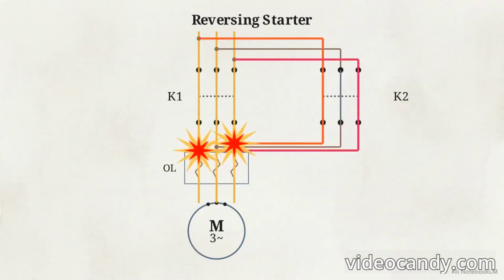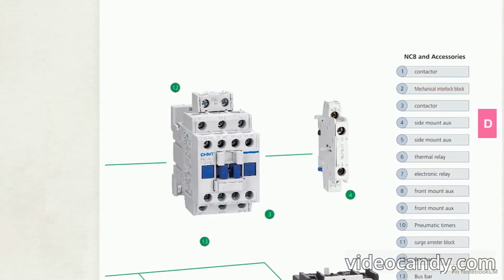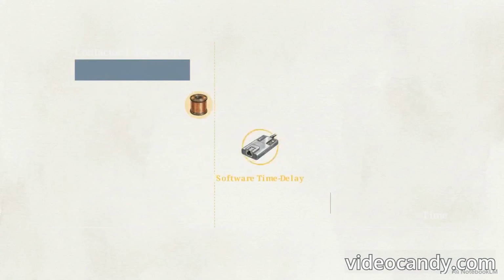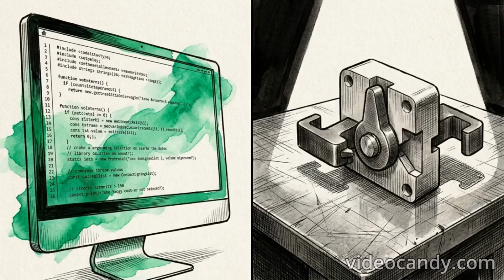A more complex application is the reversing starter. To reverse the rotation of a three-phase motor, you need two separate contactors working together to swap the connection of two phase lines. If both contactors were to close at the exact same time, the overlapping phases would create a violent phase-to-phase short circuit. To prevent this, a mechanical interlock block, seen here as item 2, is installed between the two units. It contains a physical wedge that makes it physically impossible for both armatures to be depressed simultaneously.